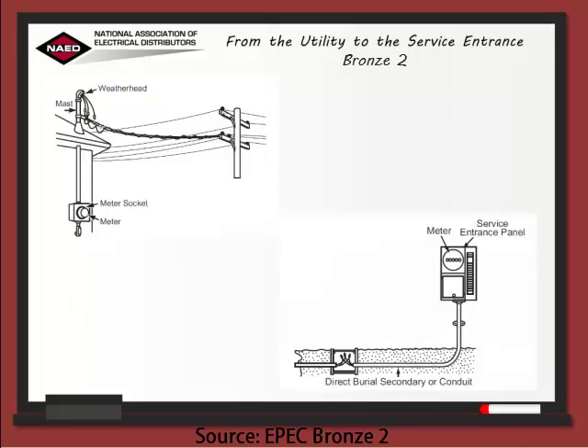Electricity is brought from the pole transformer like we just discussed. It goes to a service entrance head, also called the weather head, which is installed on the side of the house near the roof line. A galvanized rigid or intermediate conduit, referred to as the service mast, carries conductors from the service head to the meter socket, which holds the utility's watt-hour meter.